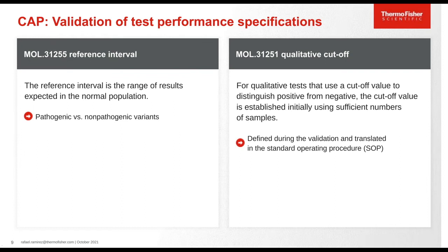Reference interval refers to the range of results expected in the normal human population. For the qualitative cutoff — for qualitative tests that use a cutoff value to distinguish a positive from a negative sample — the cutoff value is established initially using sufficient numbers of samples. It is defined during the validation and then translated into your standard operating procedures.